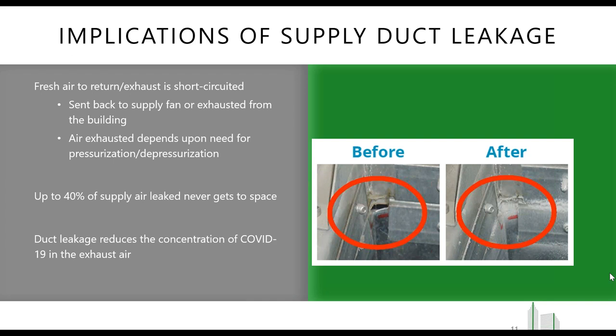So how do we stop this from happening? You think about a building and where the ducts are. Those are in spaces that we can't get to, right? They're behind walls, they're above ceilings, and there's no way we can go in with the mastic and the tape without demoing areas out and actually getting to it. So that's where AeroSeal comes in.